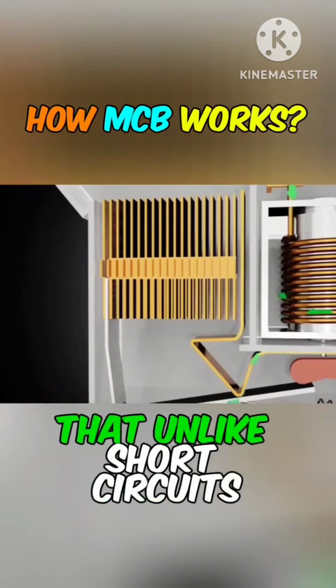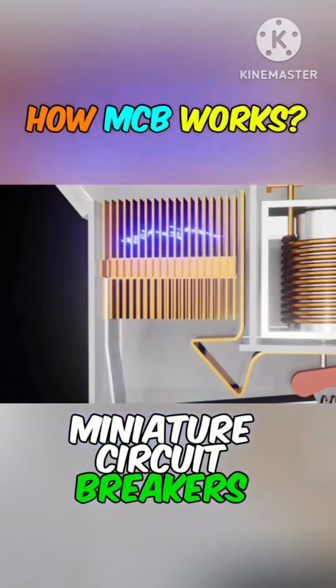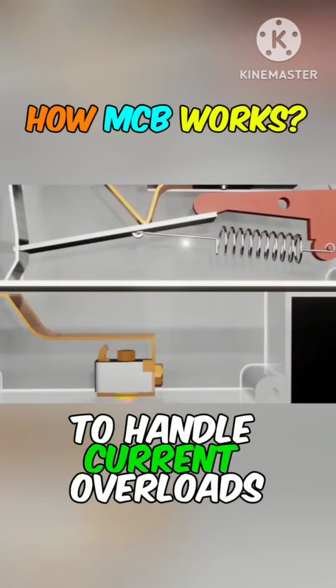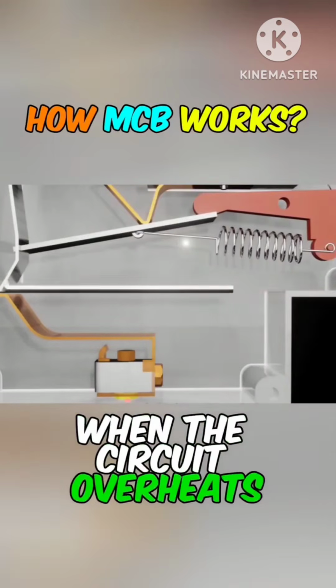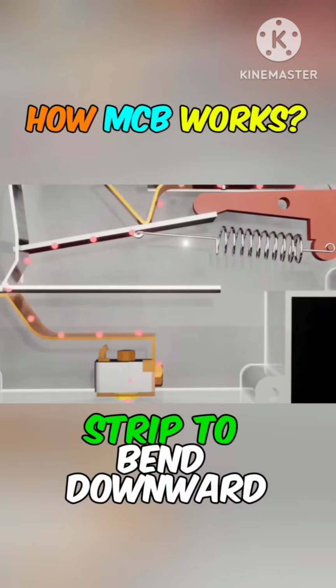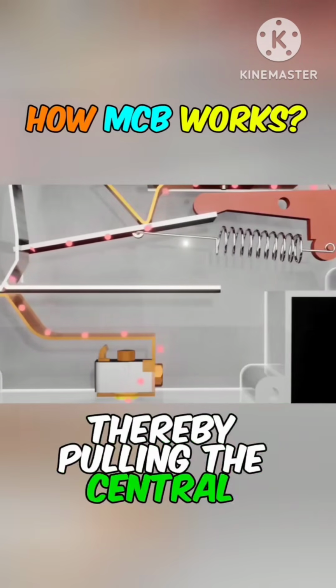Note that, unlike short circuits, miniature circuit breakers have another mechanism to handle current overloads. When the circuit overheats, it will trigger the bimetallic strip to bend downward, thereby pulling the central lever down.